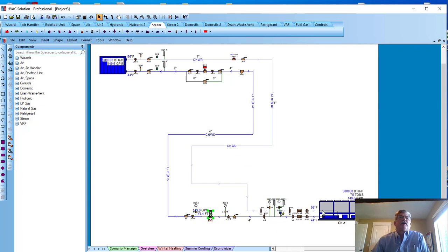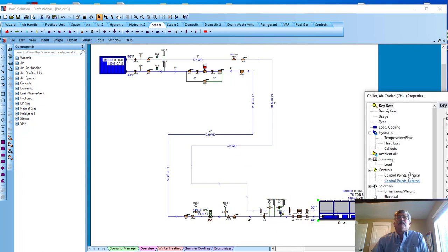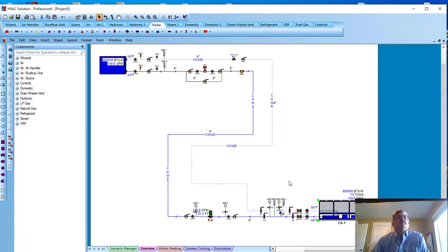But we allow every component, let me just show you, I can go in here, on that chiller on head loss, you'll see you can actually put control valves, balancing valves, you can put those in here if you're not going to show them on your diagram and refer to them in a detail sheet, and that accounts for them. Or you could just come in here and say, I want to add some miscellaneous shut-off valves and flex connectors and whatnot, and then add additional. Like I said, those are very small head. You saw that 0.1, 0.2 type on a system.